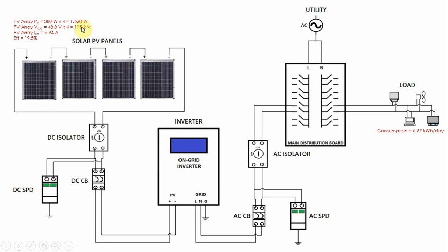The current flowing through these panels is 9.94 amps, which will also be the input current to our on-grid inverter. In step three, we determined the rated power of the inverter by taking the maximum output of our solar PV array — 1,520 watts — and based on this we choose an inverter with a sufficient power rating. In this example, we choose a 2,200-watt inverter.